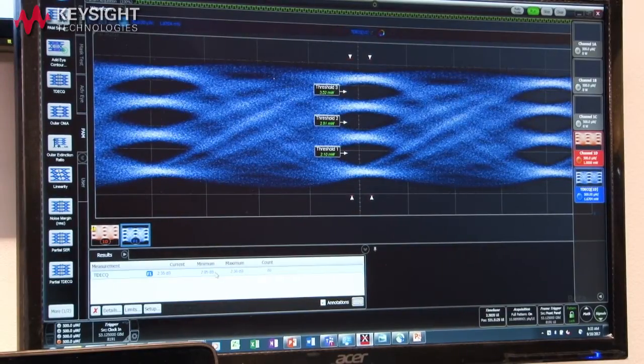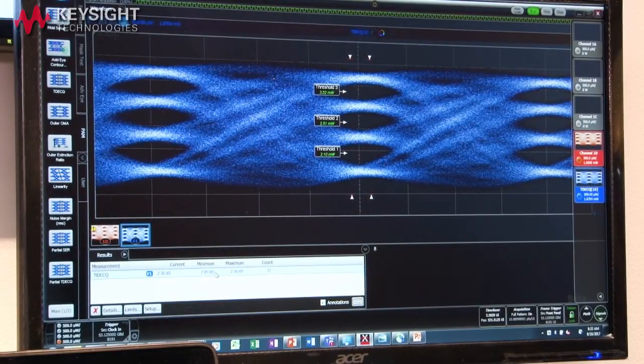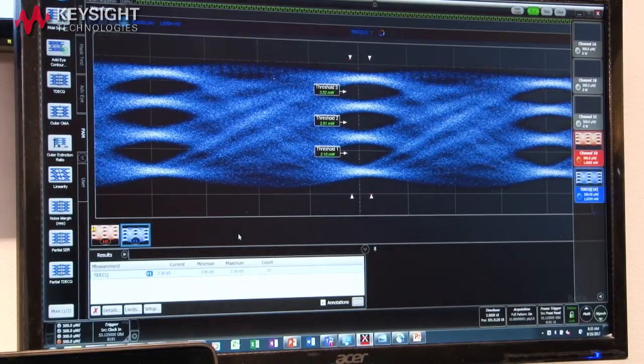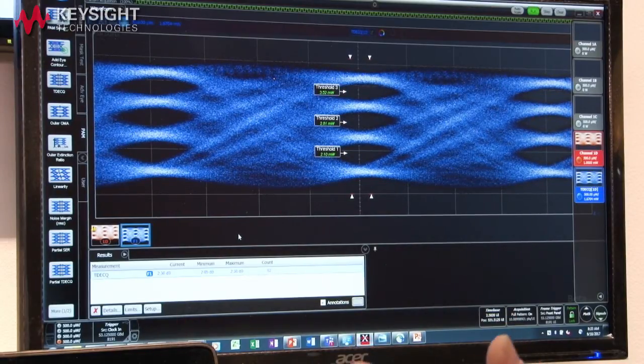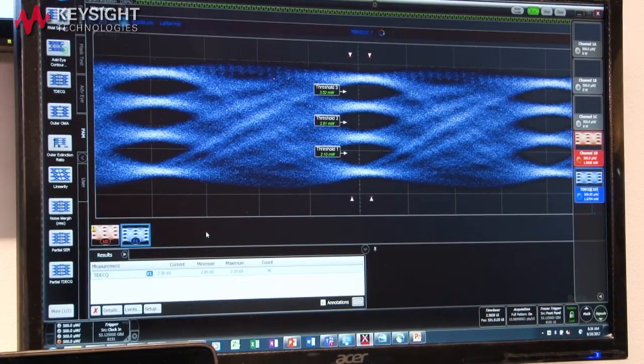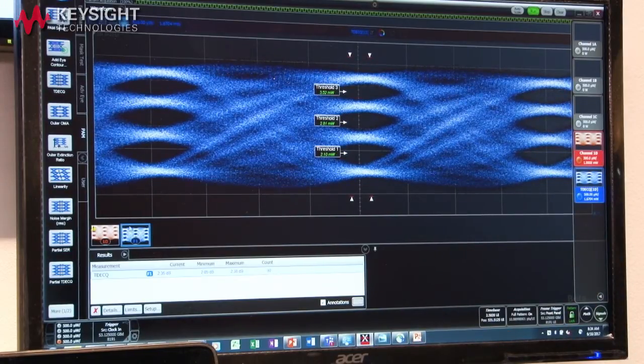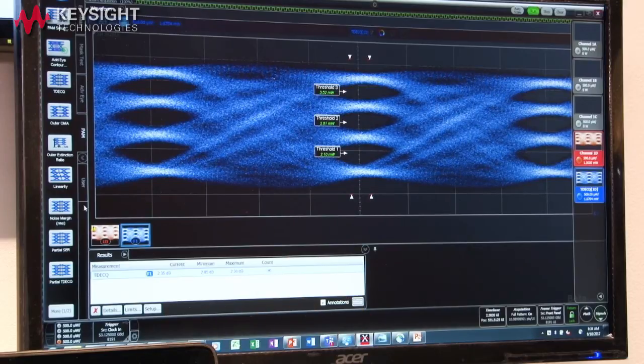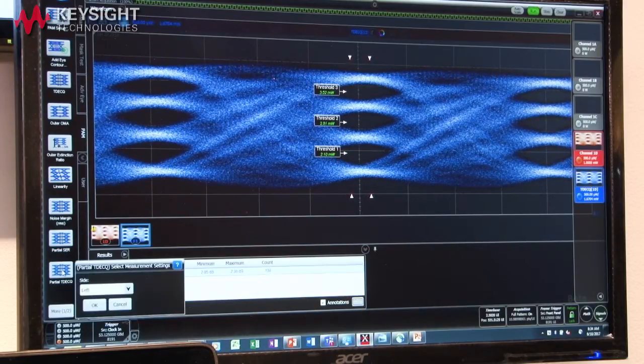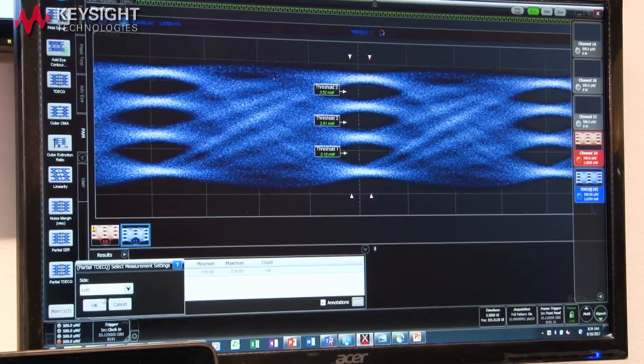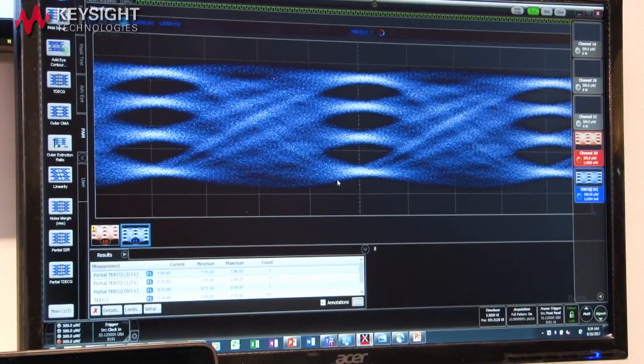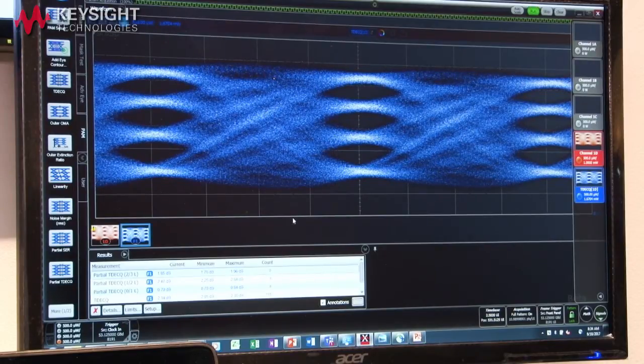In addition to making the TDECQ measurement, it's often useful to understand what are the signal parameters or elements of that signal that lead to the TDECQ value. So in addition to just TDECQ, we also have some additional measurements that allow us to see which components of that signal are actually the main contributors to the TDECQ value.